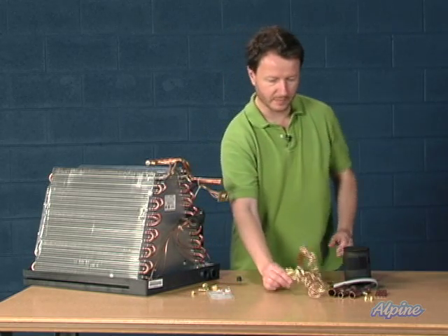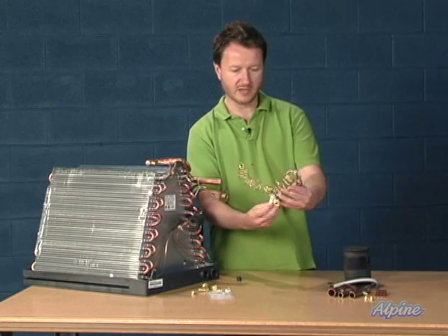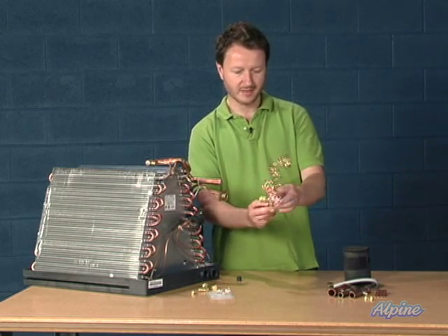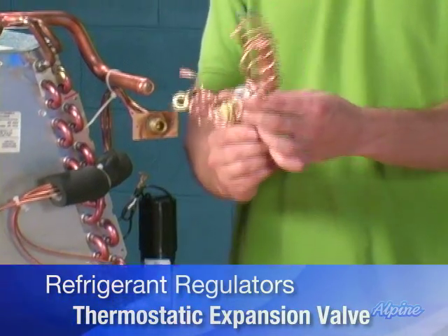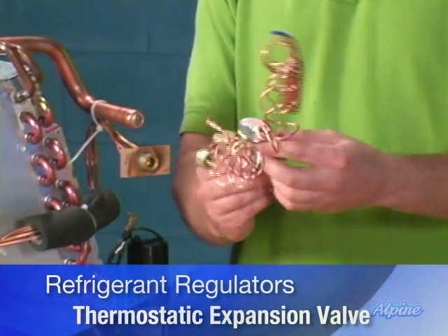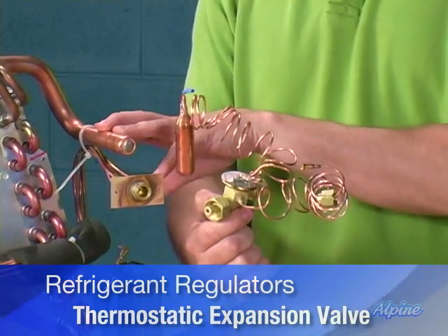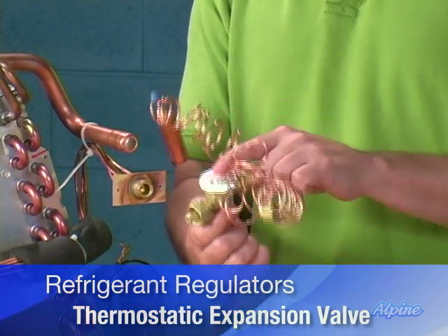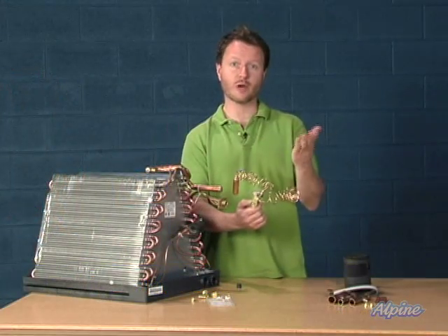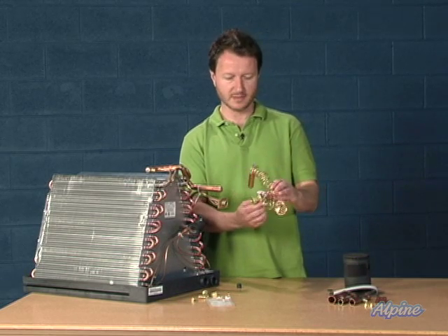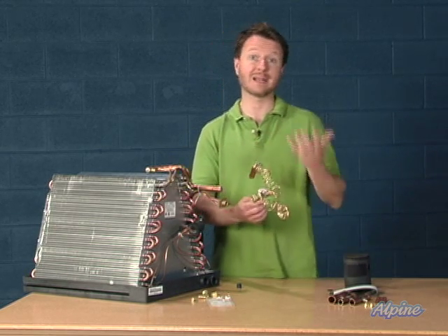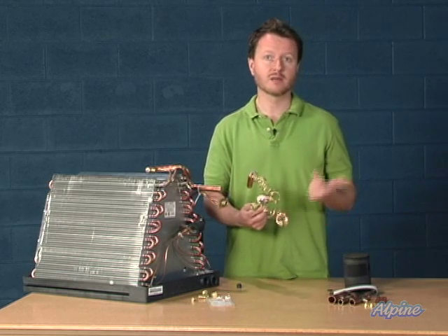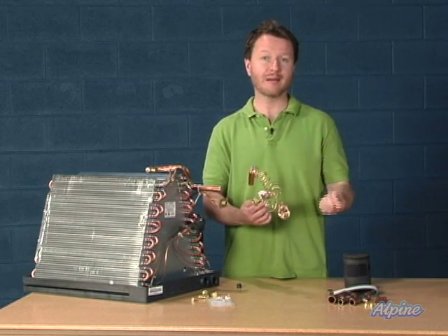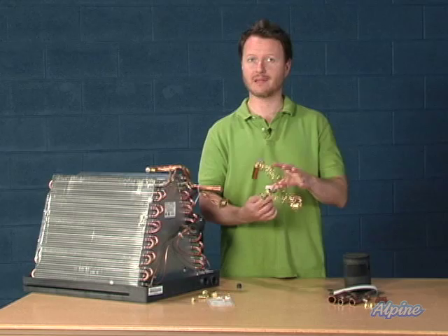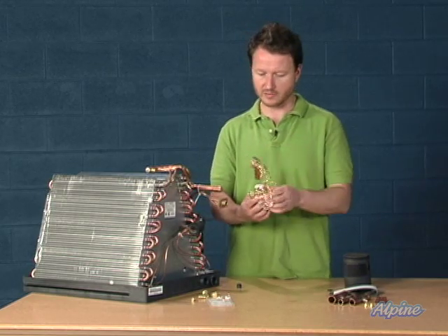Now, let's take a look at this here. This is a crazy looking slinky of sorts, but it's a really clever device that has a regulating orifice in it. So instead of just a fixed little size, this will sense the temperature of the refrigerant and change, according to the weather changes and the heat load on the building, the amount of refrigerant that flows through here. And it increases the efficiency, meaning it will still cool the home fabulously, but use less electricity to do so. And that's the big upshot to using one of these.